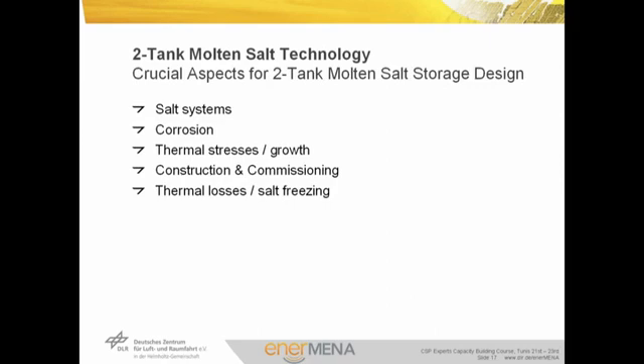The selection of the salt system is decisive for the design, since the operation temperature results from the freezing point and the maximum allowed temperature of the salt. Important for systems using molten salt is the consideration of corrosion aspects. While failures resulting from corrosion must be avoided, oversizing of the wall thickness increases the cost of the system significantly. Detailed knowledge about the corrosion process is therefore important for a cost-effective design. Detailed knowledge about the heat transfer mechanism to the environment is also important, and the cost for insulation should be compared against the efficiency losses.